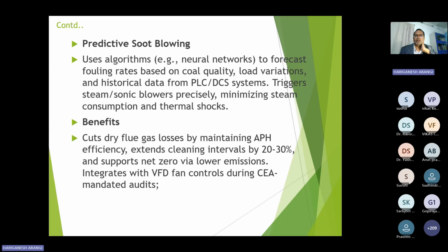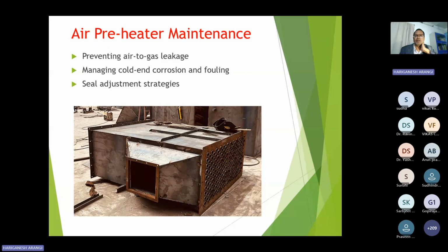So the benefits of this: it cuts dry flue gas losses by maintaining the APH efficiency and extends cleaning intervals by 20 to 30%. As I told, the cleaning intervals can be increased. Instead of 4 hours, it can be done at 8 hours. It also supports net zero via lower emissions, integrated with VFD fan control during mandated audits. This is a typical air preheater, where one side air will be there and on the ducting side flue gas will be there.